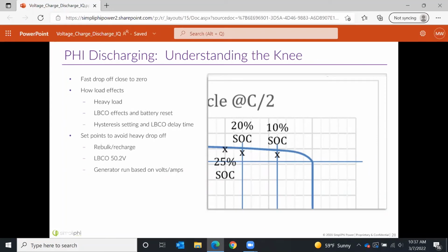What happens when you try to recharge a dead battery with an inverter charger or charge controller is that the startup current just to turn on the inverter, or charge the capacitors within it, will draw the battery back down to BMS shutdown because there's so little energy remaining. To combat that, you need an external charger—one that provides power to the battery without ever seeing a voltage on the terminals.